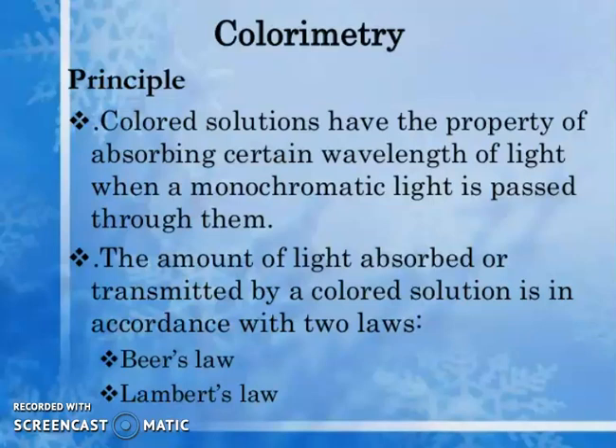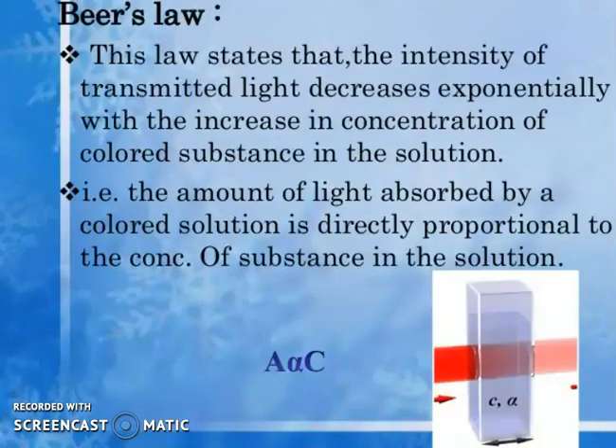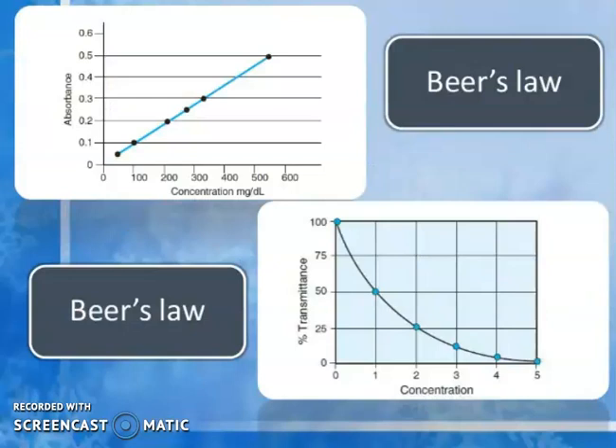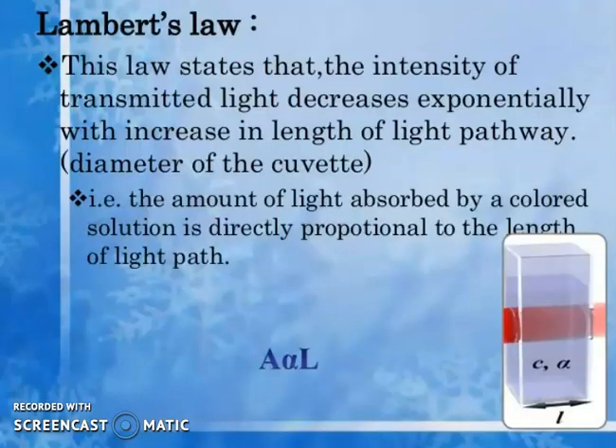Colored solutions absorb certain wavelengths of light when monochromatic light is passed through them. The amount of light absorbed or transmitted is governed by two laws: Beer's law and Lambert's law. Beer's law states that the intensity of transmitted light decreases exponentially with increasing concentration of the colored substance — the amount of light absorbed is directly proportional to the concentration. Lambert's law states that the intensity of transmitted light decreases exponentially with the length of the light path (diameter of the cuvette) — the amount of light absorbed is directly proportional to the path length.